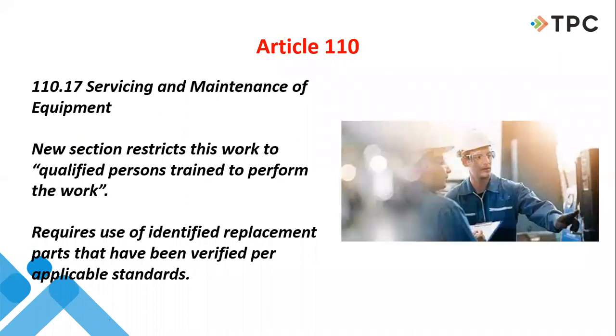In the 70E, in the arc flash standard, they are very adamant that qualified persons be the people that are allowed to be in this area, allowed to be exposed to these hazards, allowed to enter into this boundary, and so on and so forth. 110.17, with regards to the servicing and maintenance of equipment, now restricts that work to qualified persons. It requires the use of identified replacement parts that have been verified by, or according to, certain standards.